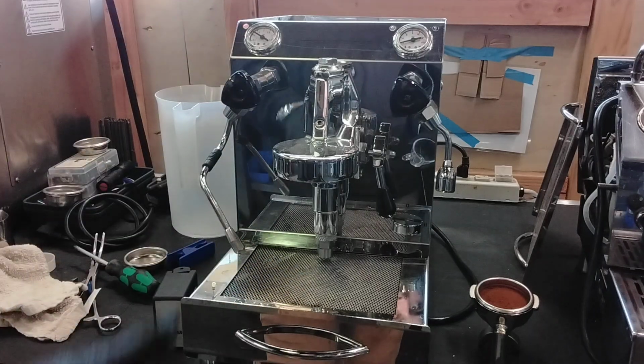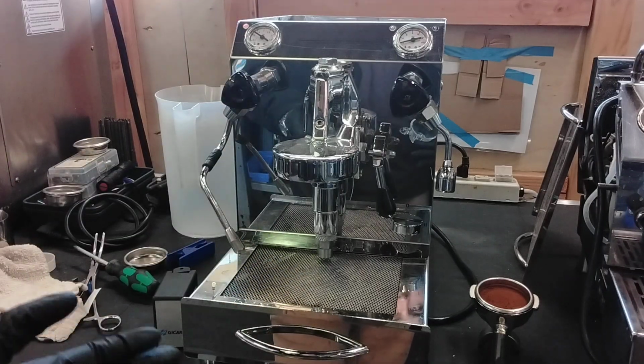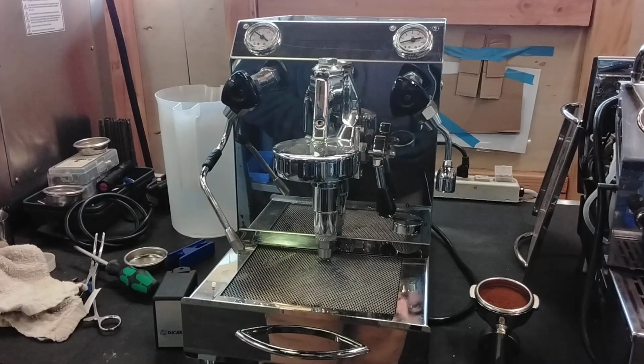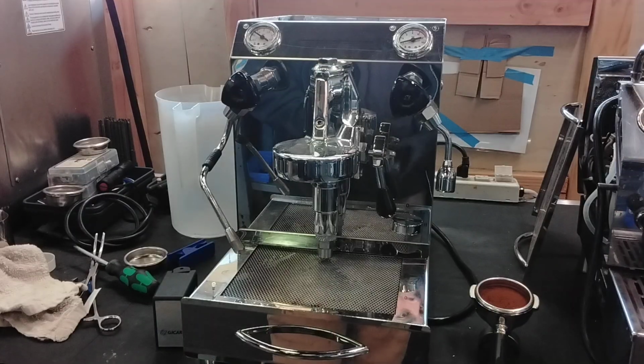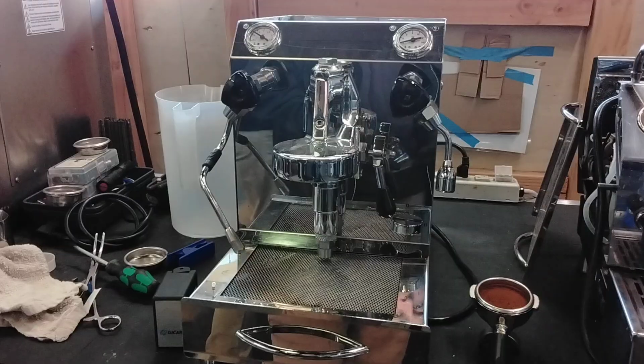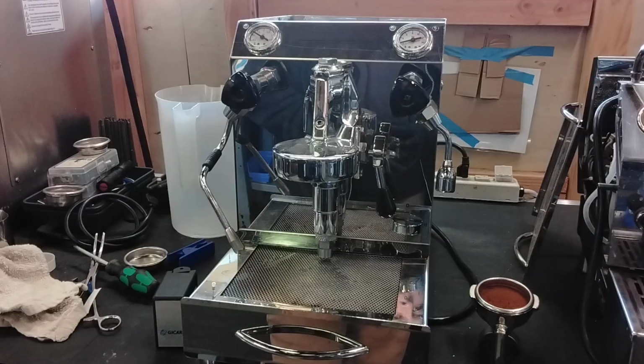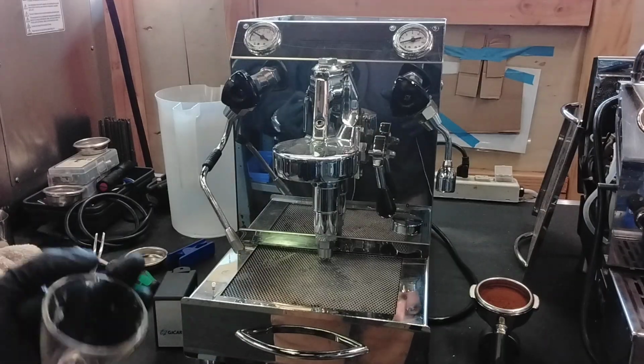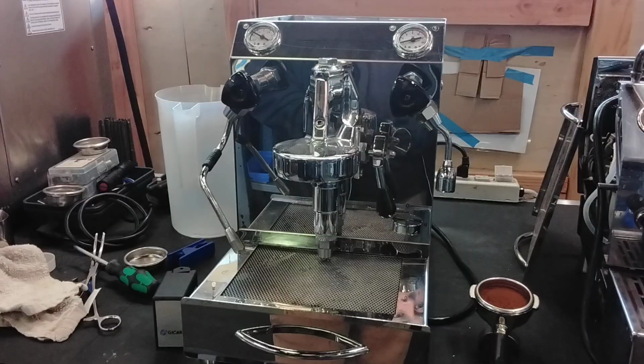Mainly, the machine was working fine, however the fill probe that was inside the machine was overfilling the boiler, and when I took it out it was really bad with scale. So I took it out, polished it, cleaned it up, put it back in, and it works great now. So now you have a lot of room for steam inside of your steam boiler.